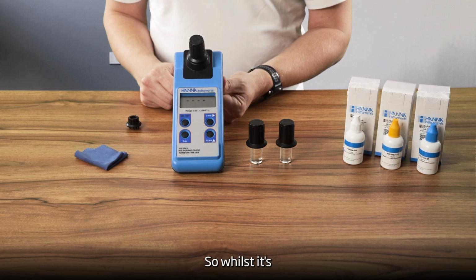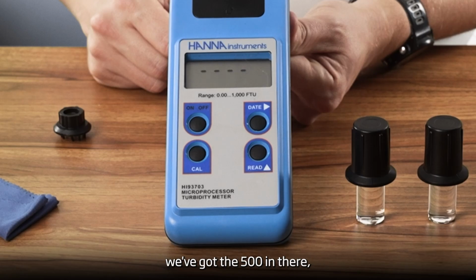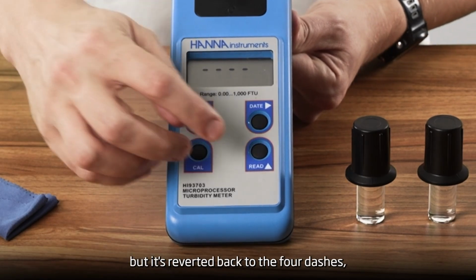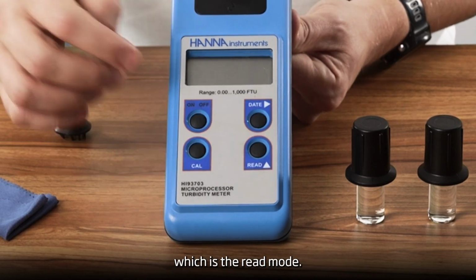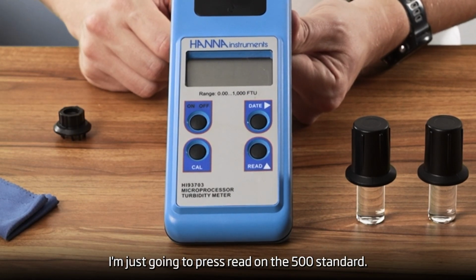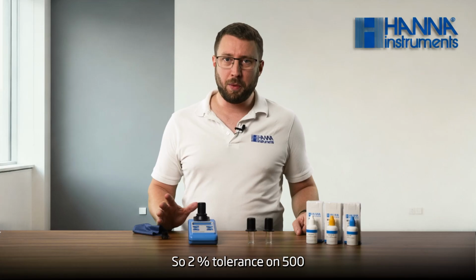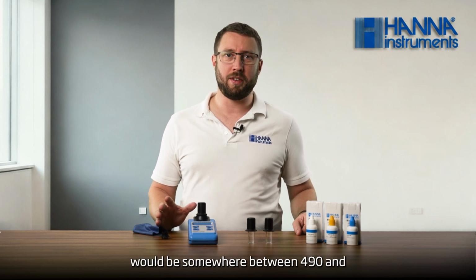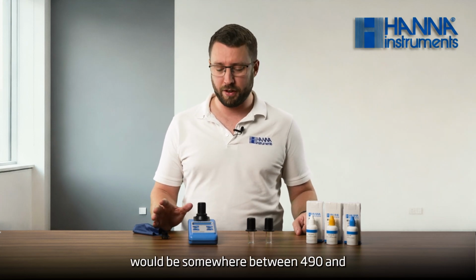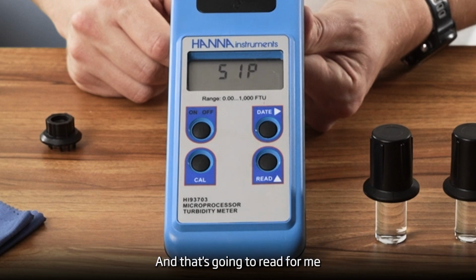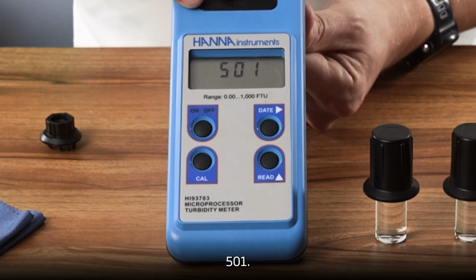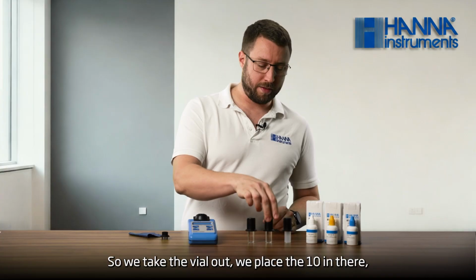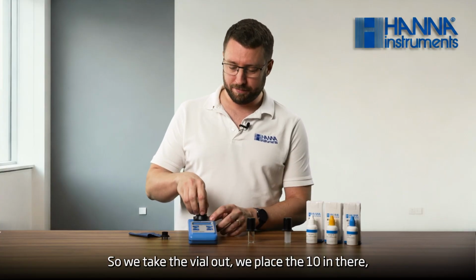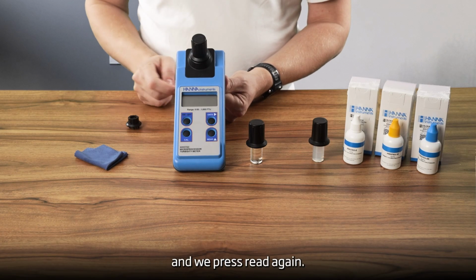So whilst it's finished the calibration mode, we've got the 500 in there, but it's reverted back to the 4 dashes, which is the read mode. I'm just going to press read on the 500 standard. So 2% tolerance on 500 would be somewhere between 490 and 510 that we would be happy with. And that's going to read for me 501. So we take the vial out, we place the 10 in there, and we press read again.